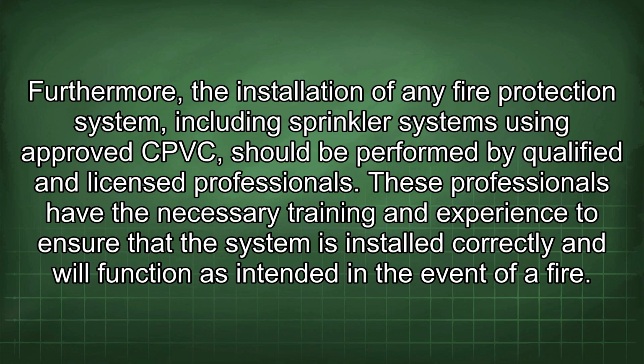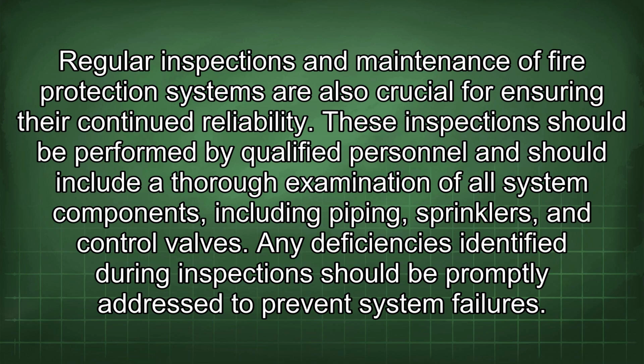Furthermore, the installation of any fire protection system, including sprinkler systems using approved CPVC, should be performed by qualified and licensed professionals. These professionals have the necessary training and experience to ensure that the system is installed correctly and will function as intended in the event of a fire. Regular inspections and maintenance of fire protection systems are also crucial for ensuring their continued reliability. These inspections should be performed by qualified personnel and should include a thorough examination of all system components, including piping, sprinklers, and control valves. Any deficiencies identified during inspections should be promptly addressed to prevent system failures.